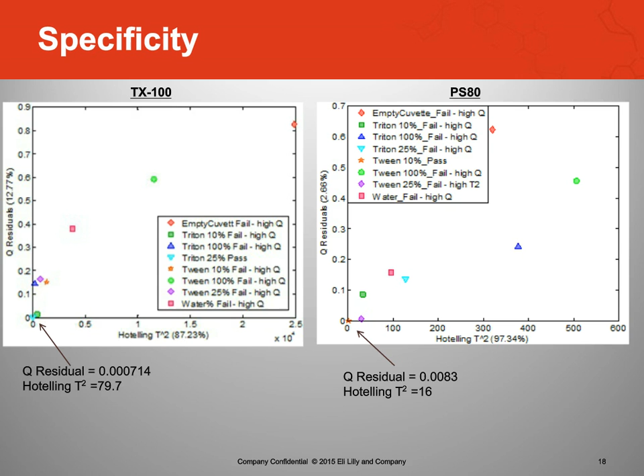So I also talked a little bit about what if there's user error. We noticed that on the particular instrument we're using, if the analyst didn't insert the laser probe completely into the cuvette holder, there might be a gap. So what does that gap do? Well, it turns out if there's a 1 or 2 millimeter gap, for Triton at least, the limit, again, this is the Q limit, if they go to 3 millimeters, they'll go above the limit and fail.